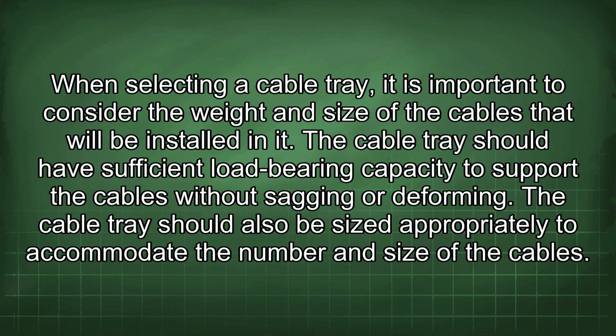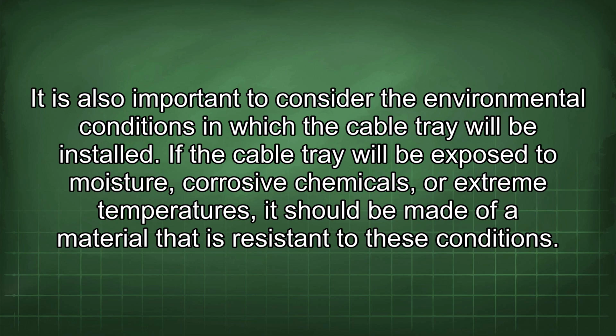When selecting a cable tray, it is important to consider the weight and size of the cables that will be installed in it. The cable tray should have sufficient load-bearing capacity to support the cables without sagging or deforming. The cable tray should also be sized appropriately to accommodate the number and size of the cables. It is also important to consider the environmental conditions in which the cable tray will be installed. If the cable tray will be exposed to moisture, corrosive chemicals, or extreme temperatures, it should be made of a material that is resistant to these conditions.